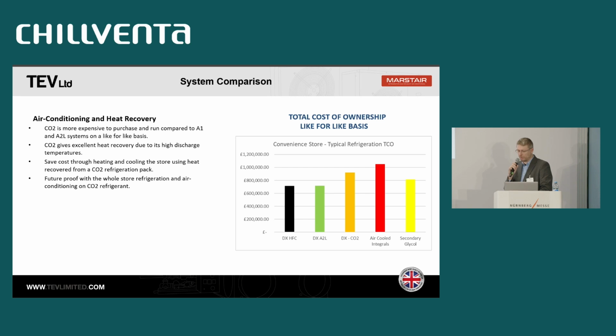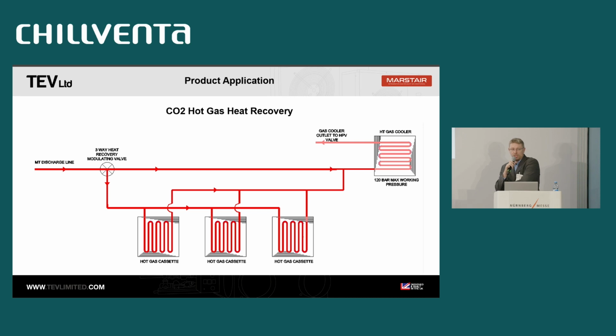Okay. So now I'm going to talk a little bit about the application of the heating side. So it's pretty easy, really. In terms of how you apply it, you'll have a pack system, and what you do is you take the gas off the main discharge line off the compressors. Normally you have a diverting valve, and you would divert the hot gas away, prior to the main gas cooler, and put it through the heating cassettes. And that way you recover the heat. Now, how you apply it is a little bit more complicated, which I'll come into a bit. But in terms of the actual physical setup, they're generally applied like this on the heating side.